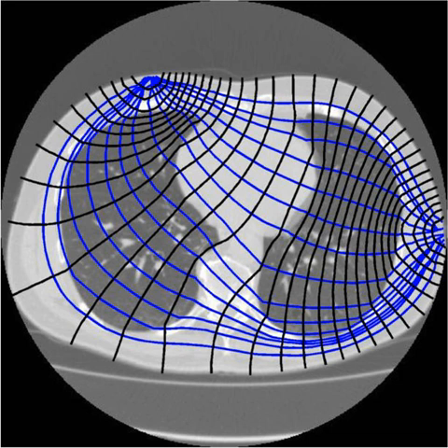Improving the signal-to-noise ratio, e.g. by using active surface electrodes, further reduces imaging errors. Some of the latest EIT systems with active electrodes monitor electrode performance through an extra channel and are able to compensate for insufficient skin contact by removing them from the measurements.